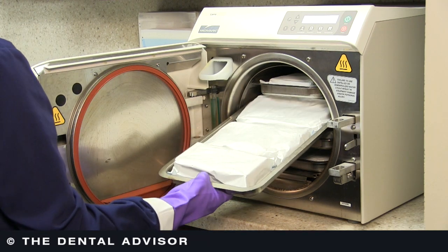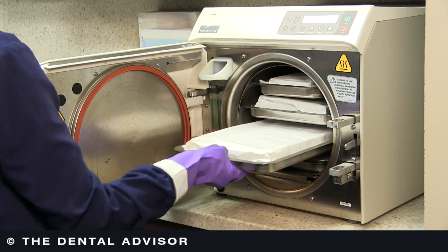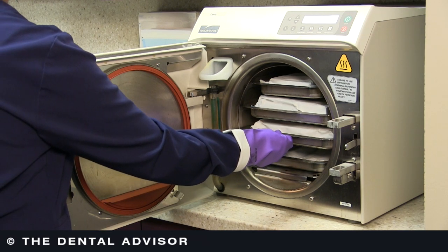Making sure that they're dry and that we're not overloading the sterilizer is important — in a big clinic running autoclaves all day, it's easy to want to put too many instruments in. Can the pouches overlap a little or do they need to not touch at all? Strictly speaking, they shouldn't be touching and the best thing is if they're slightly at an angle. The critical factor is whether the sterilant can reach all areas of the packaging and penetrate it to reach the instruments. If pouches are overlapping and stuffed together, the sterilant can't get between them, compromising the whole process.